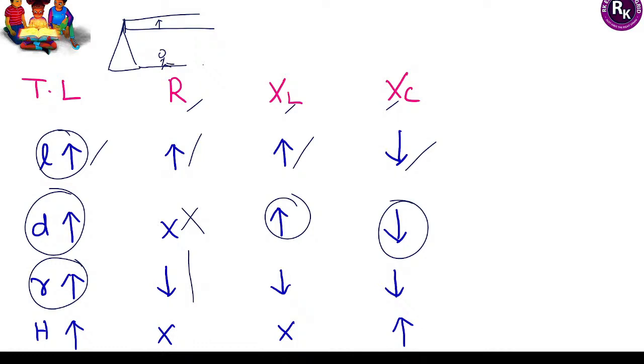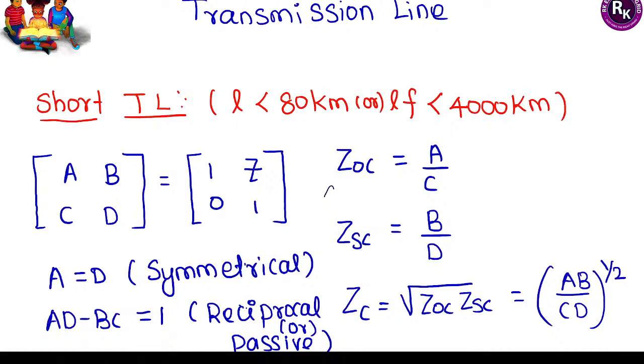Increasing the radius of the conductor: resistance decreases, inductive reactance decreases, and capacitive reactance also decreases. Increasing the height of the tower (height from ground): resistance does not change, inductive reactance does not change, but capacitive reactance increases.